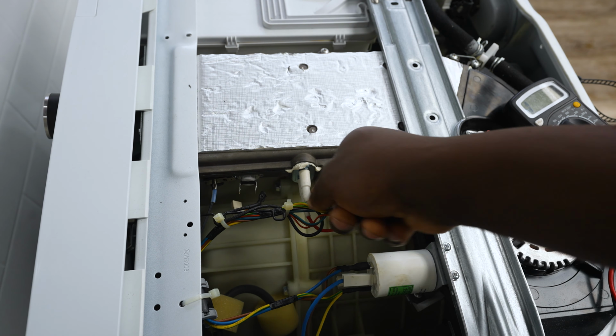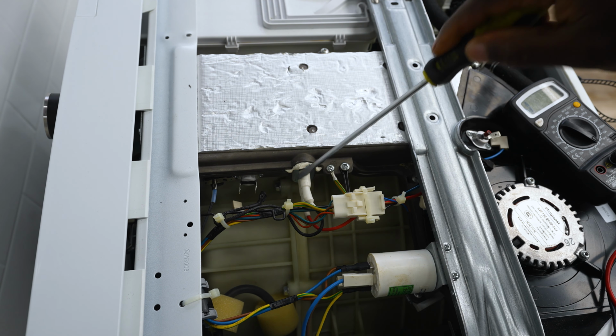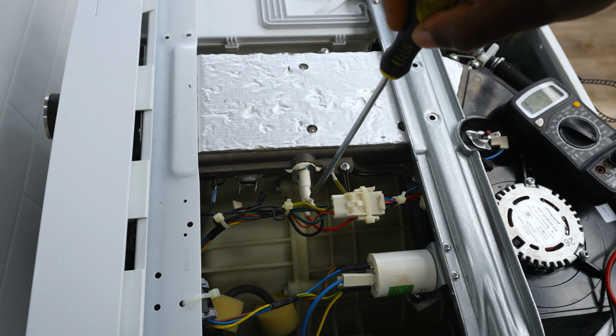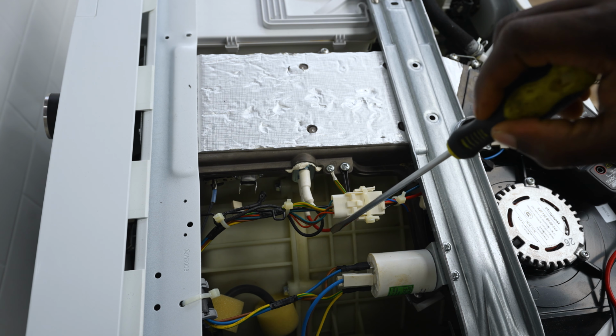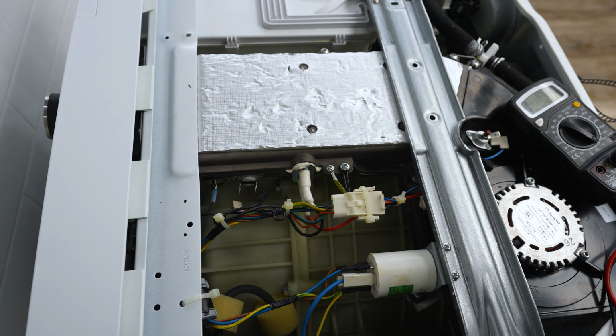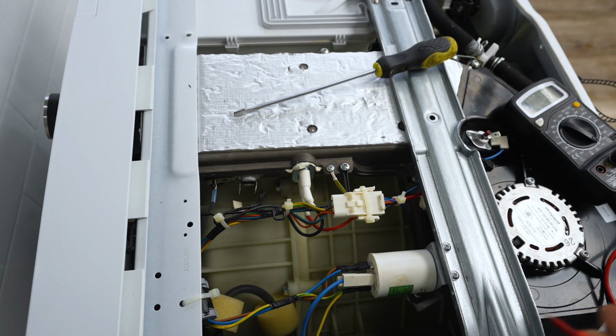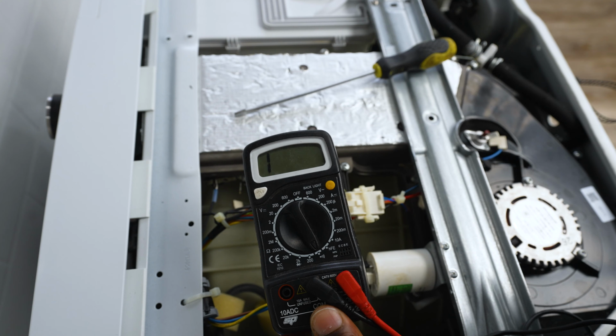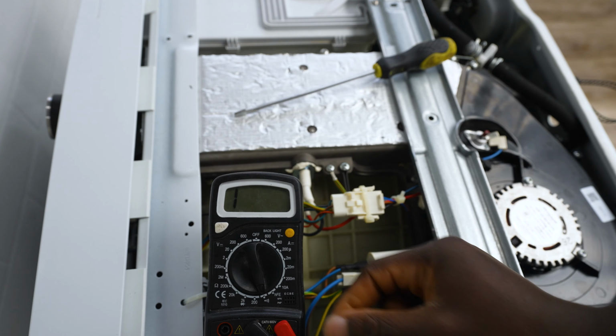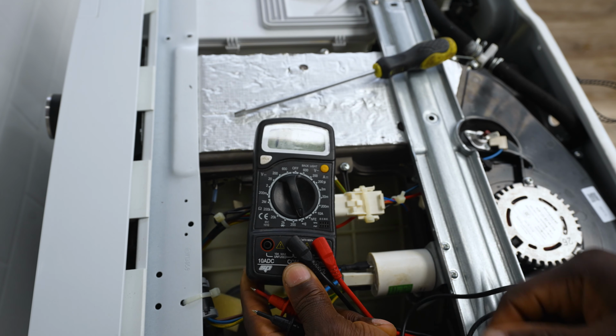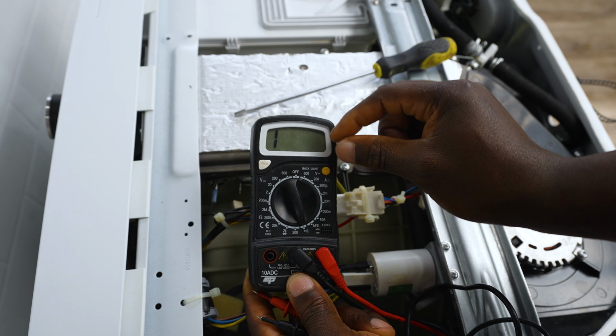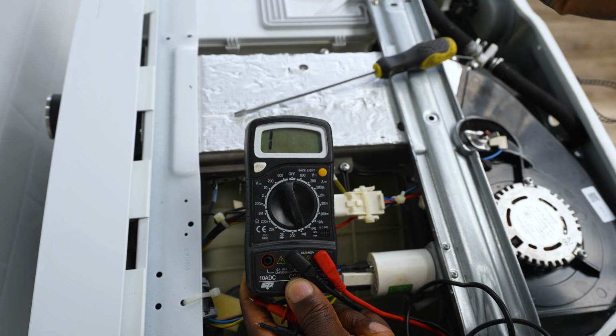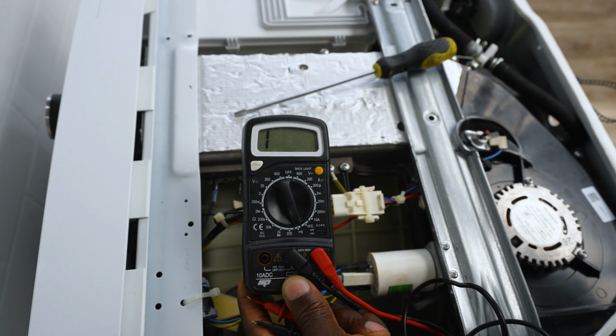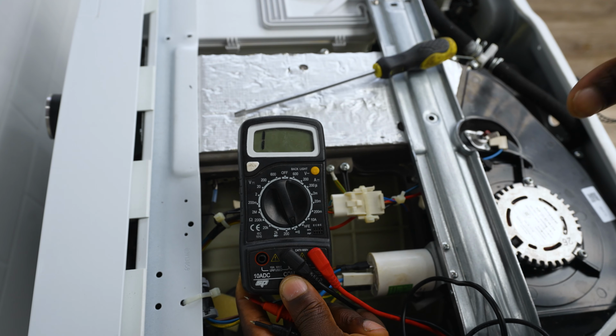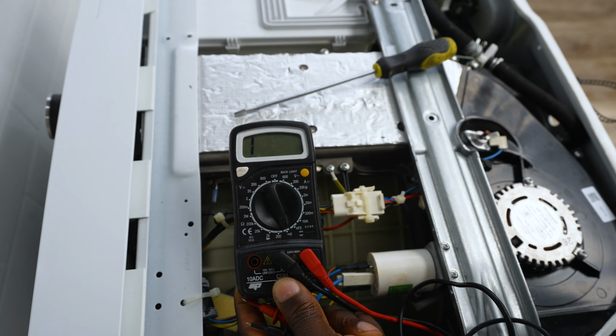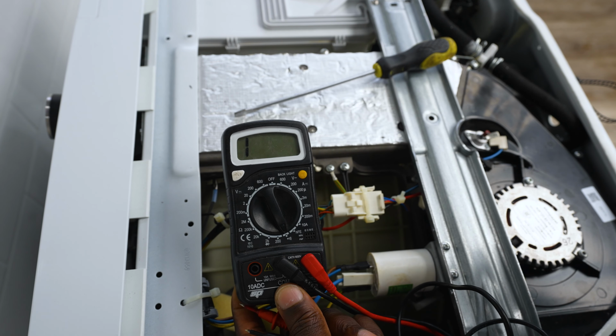The heating element is this one, and there's a red and a black wire coming out of it. We're going to get our test meter, turn the dial, and put it onto measure ohms, so we measure the resistance. We can also do continuity, so let's start with continuity and see if the heating element is working.